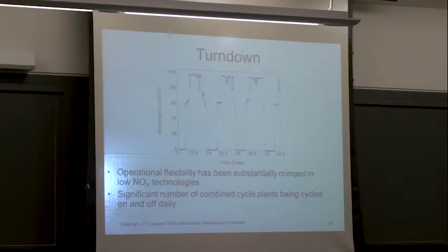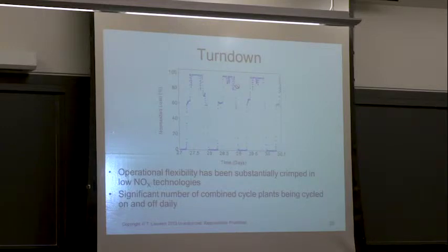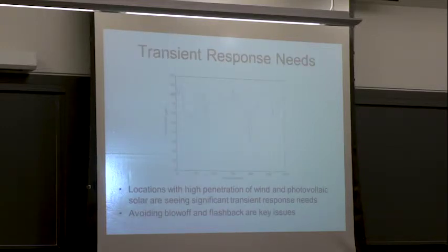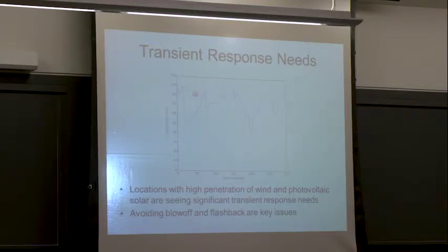And by the way, the reason for a lot of this is that the overall landscape for power generation has changed a lot. I'll get into that in this next slide. There's a lot of wind and solar on the grid nowadays, and those are usually dispatched first, and so the power plant is usually following those. In fact, this next slide shows the power generated by a power plant as a function of time. Now instead of days, it's minutes. You can see it's bouncing around all over the place. What's happening is this particular power plant is basically following renewables. And renewables are non-dispatchable, right?